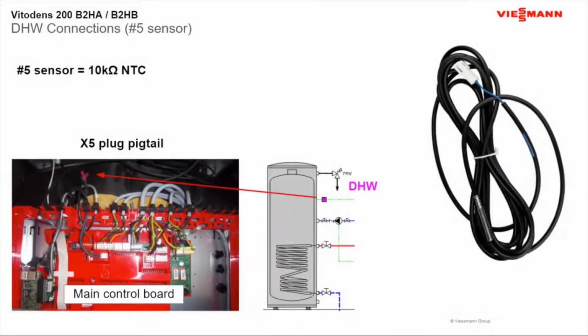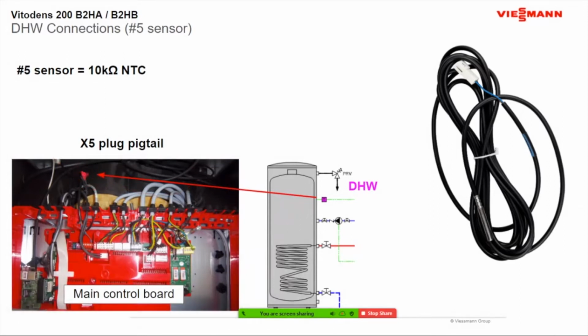Same with our domestic sensor on the boiler itself. When you take the cover off, if you look on the left-hand side of the boiler, you'll see these 2 little red tabs that say number 5 on it, because our number 5 sensor has always been our domestic sensor. So all you're going to do is plug that number 5 sensor right into the 2 plugs on there. And a lot of times it's hidden behind the pipe on the boiler here. And so they're there.